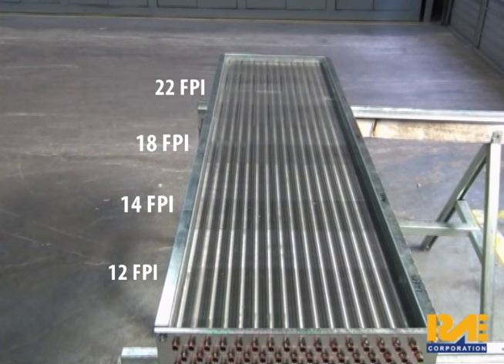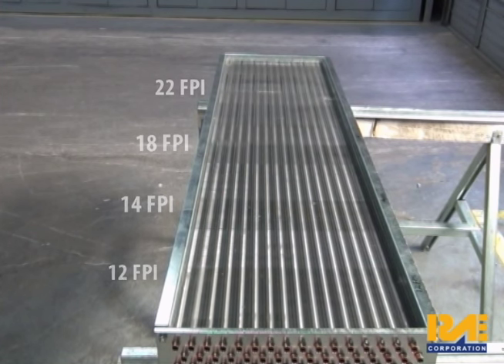None of these fin patterns include any louvered openings. We will sift the fine dirt over each portion of the coil and then clean the coil with compressed air to illustrate the potential impact to long-term efficiency at the various fins per inch.